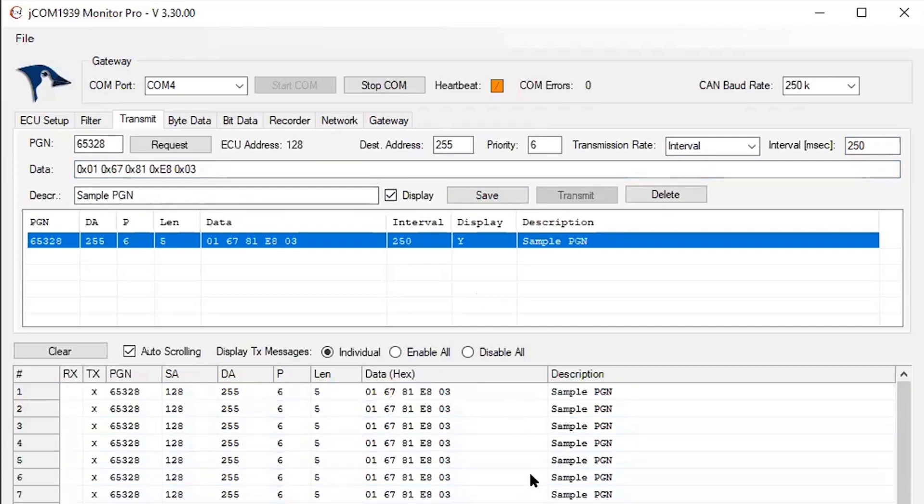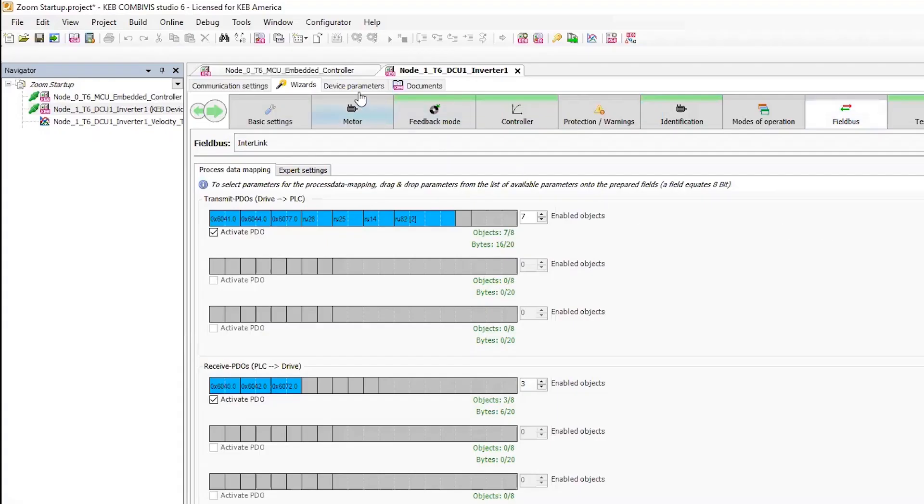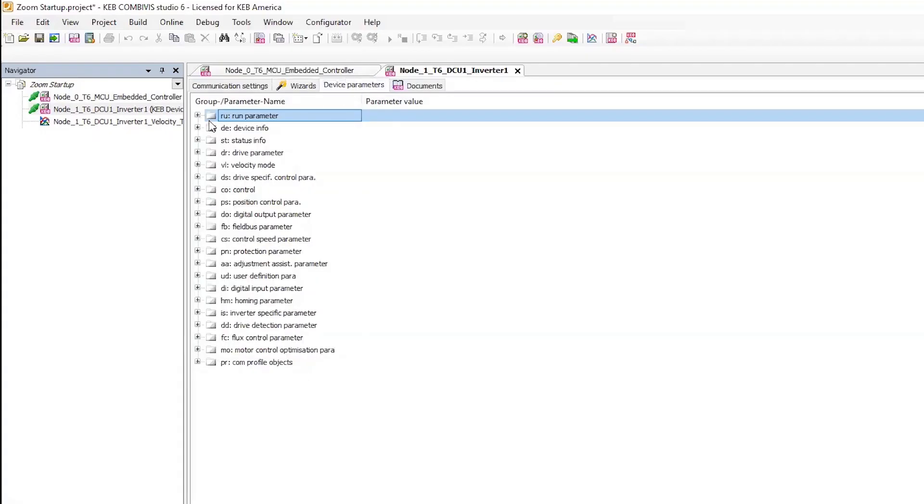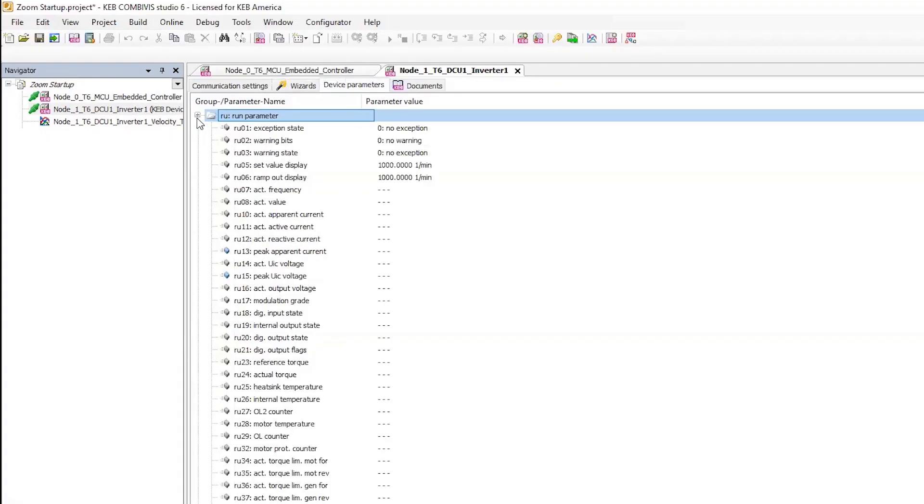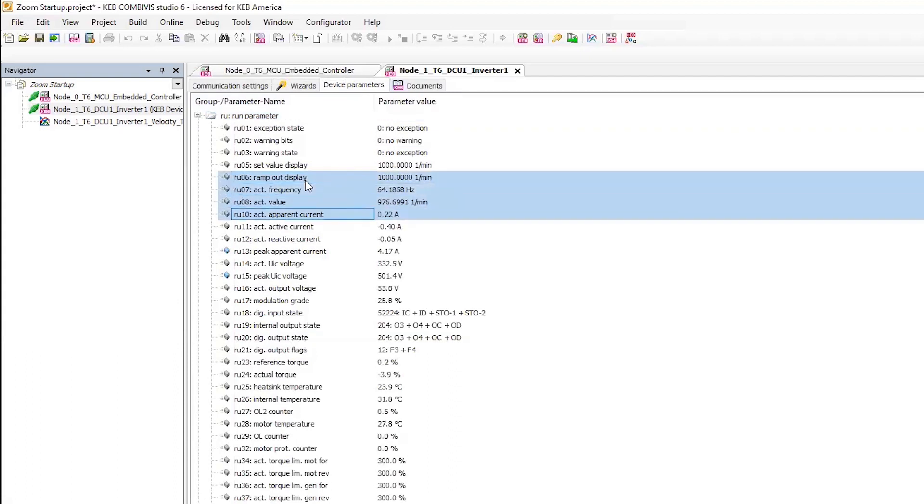So you can see communication there. What I'm sending is essentially a start command and a speed command. So I can go back to my CombiVis program, go to device parameters and open up the RU parameter group. And here I can see a speed command being given as well as a feedback command, current and voltage output.